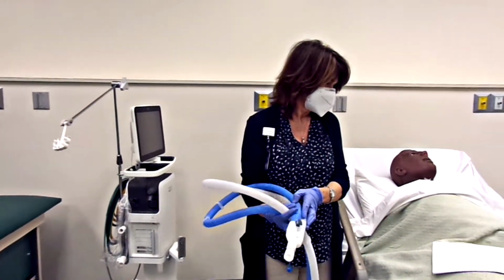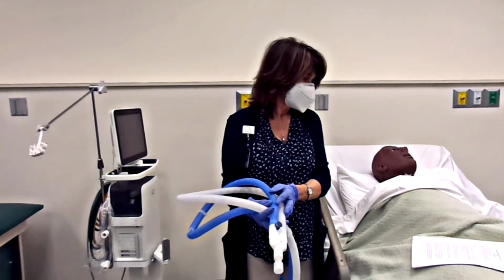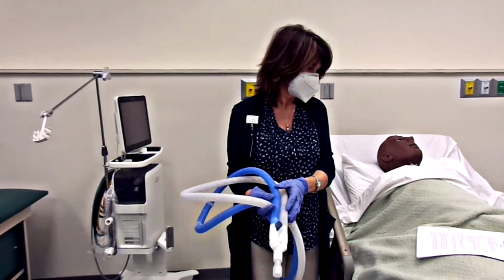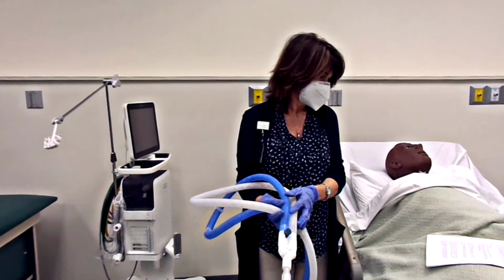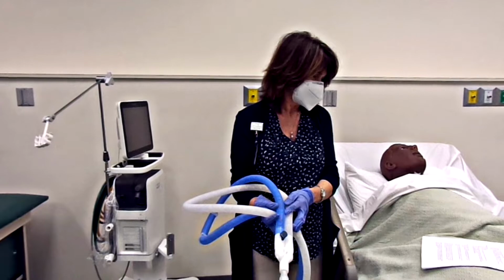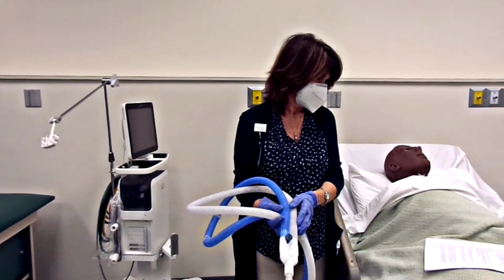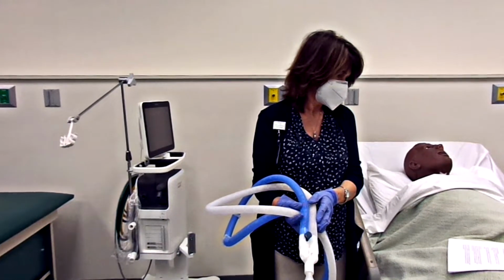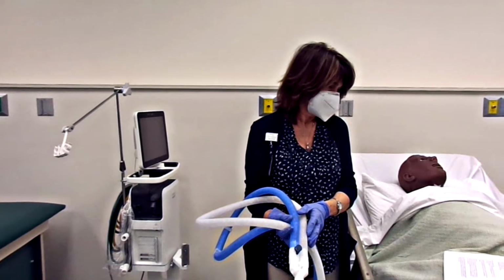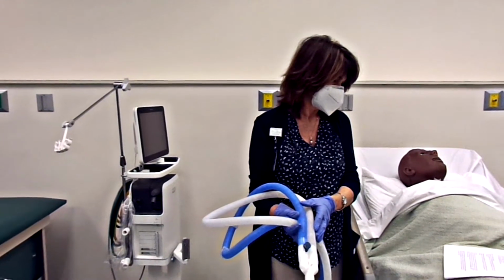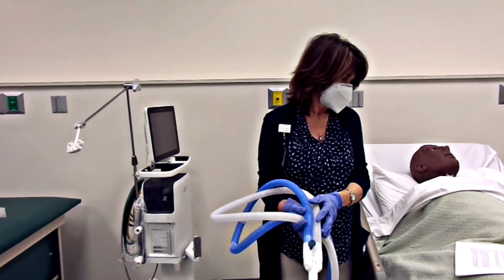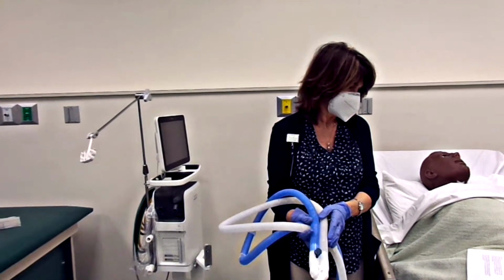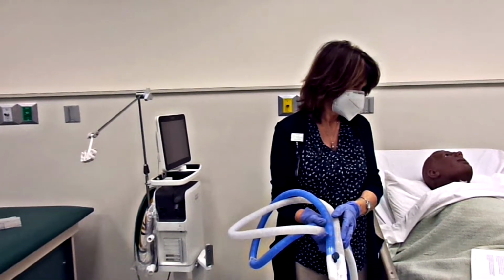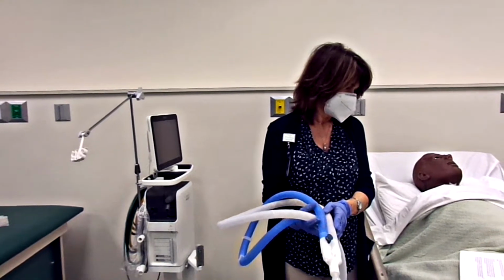Expiratory limb. The expiratory limb is connected to the ventilator, and exhaled gas from the patient will go inside the ventilator where the exhalation valve is located. Although not visible, the valve closes during inspiration, so the flow of gas can only go into the patient's lungs. It opens on exhalation to allow the gas to leave the patient's lungs. It also has transducers which monitor flow, pressure, and volume.